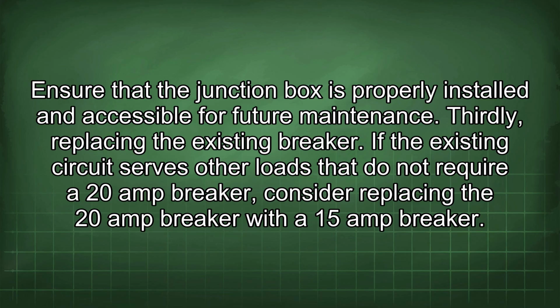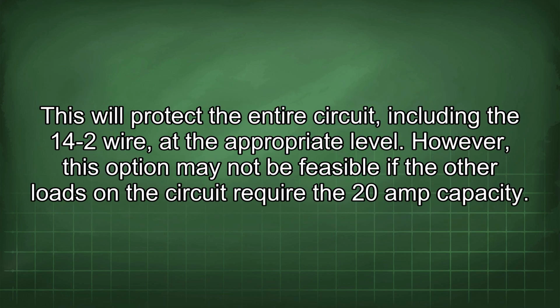Thirdly, replacing the existing breaker. If the existing circuit serves other loads that do not require a 20-amp breaker, consider replacing the 20-amp breaker with a 15-amp breaker. This will protect the entire circuit, including the 14-2 wire, at the appropriate level. However, this option may not be feasible if the other loads on the circuit require the 20-amp capacity.